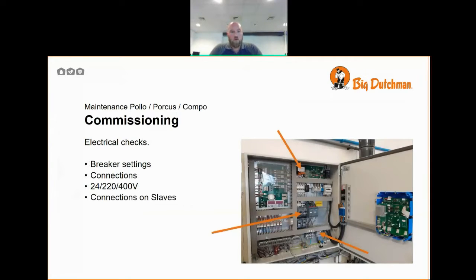Electrical checks. We need to check the breaker settings so that each motor group is set up for the correct amperages that each pump has fitted. Check all connections are tight. Check the 24 volt, the 220 volt, and the 400 volt voltages. Check the supplies are correct, and any connections to any slaves.